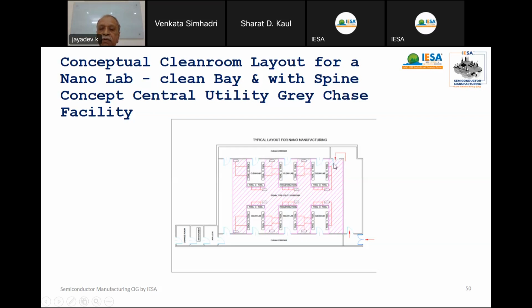So here, the maintenance people can come through the utility corridor and go back. The clean room people can go here and do the process. They are in a clean corridor like this, and this is the dirty corridor, called a gray chase, and this is the clean bay. This concept is called a spinal cord. All along the spinal cord, we connect whatever we like. Otherwise, suppose I do it in a conventional way, I run all the clean rooms with a central corridor, and we connect to this, but utilities run all along. So the length of the pipes, pressure drops, and cost can also be reduced.